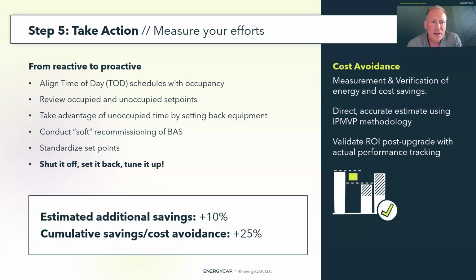Get out in your buildings, audit the buildings, make sure as the HVAC systems are running, it's tied to the occupancy that's taking place in the buildings. Too many times I saw buildings running well into the evening after people went home, or they come on way too early in the morning. This is a huge opportunity. And what's great about the software is you can see this and you can also quantify the benefit in order to motivate you to capture those savings.